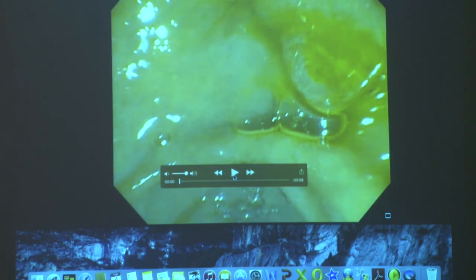We have slightly different experiences because we are reusing equipment — after a certain use, sphincterotome tips become not as smooth. You find it a little more difficult with reused equipment. The wire-guided technique is excellent, but when you reuse wires, they are totally different from a new wire after ten uses. Those are things you learn and adapt to — we've achieved reasonably good success with what we have, so it is doable.